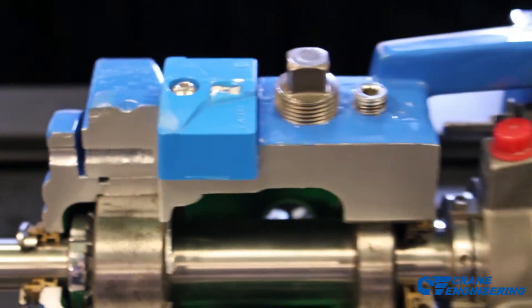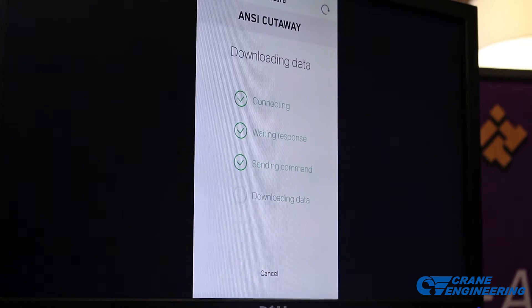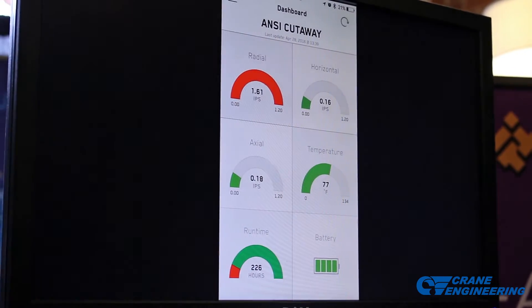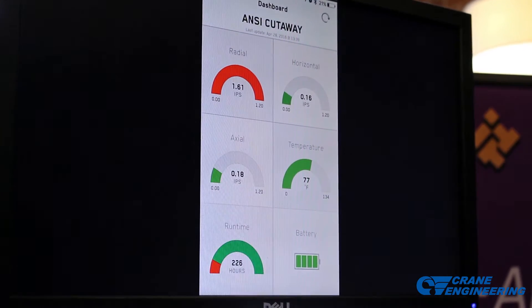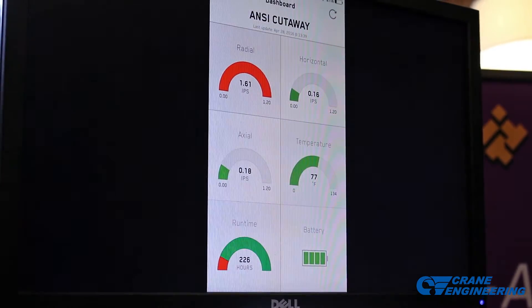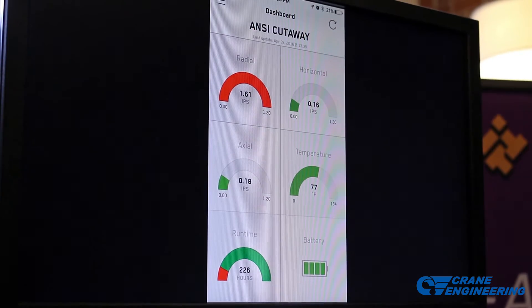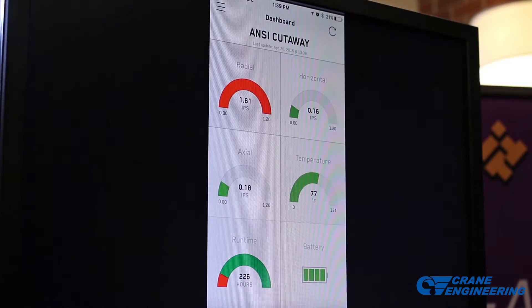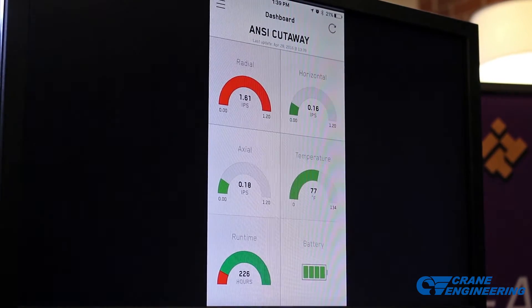If we want to dive into that and take a closer look at the machine that's in an alarm condition — the iAlert is looking at the data continuously. The dashboard gives us real-time data in all three axes; it's a tri-axial accelerometer. It also tracks temperature, run time, and battery life. Battery life on the iAlert is three to five years depending on usage.